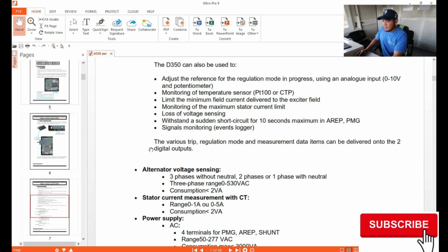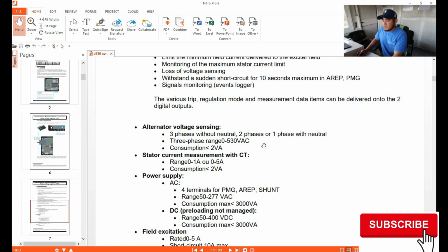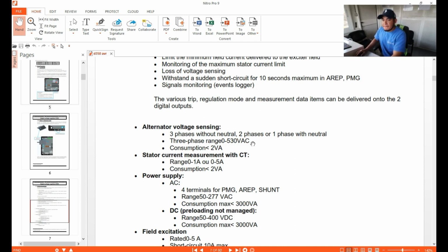The various regulation modes and measurement data can be delivered into two digital outputs. For alternator voltage, this is the sensing range. Three-phase without neutral is only the delta connection like that. Two-phase or single-phase with neutral, three-phase range is 0 to 530 volts AC. So you have the biggest range of voltage sensing. I think this depends on the applications you use it for. The consumption stated here is 2 volt amperes.